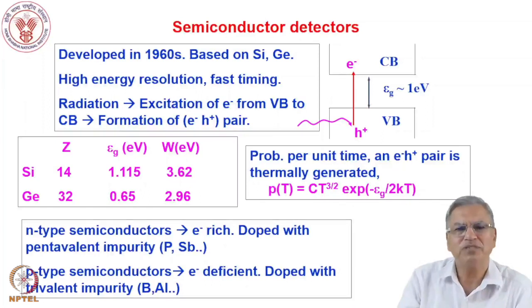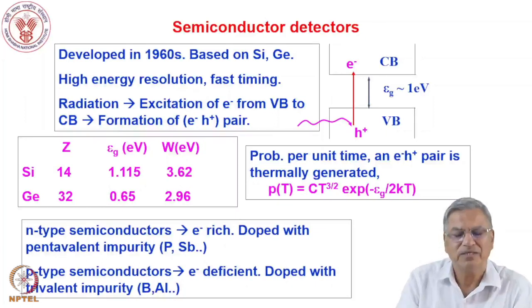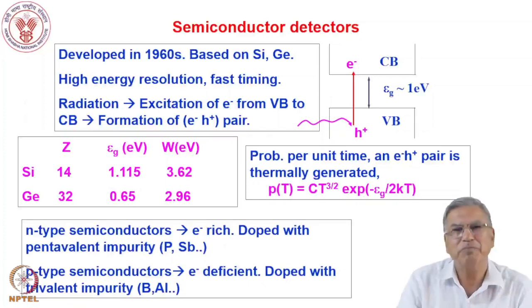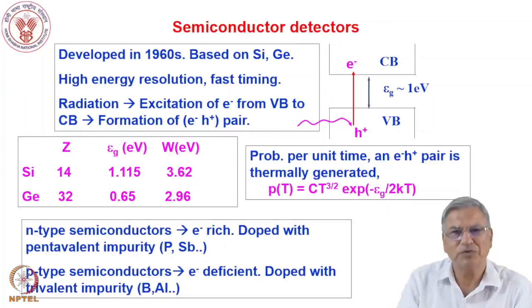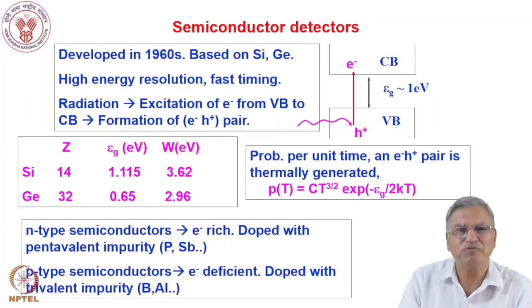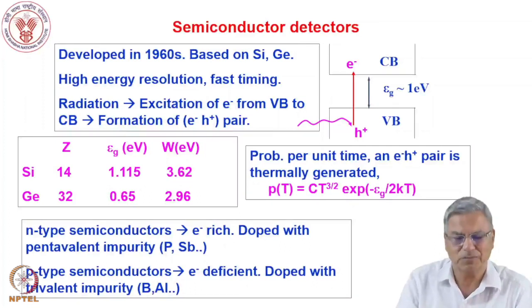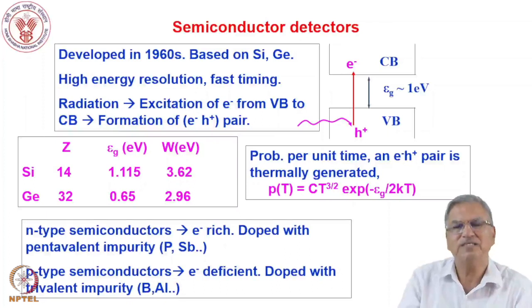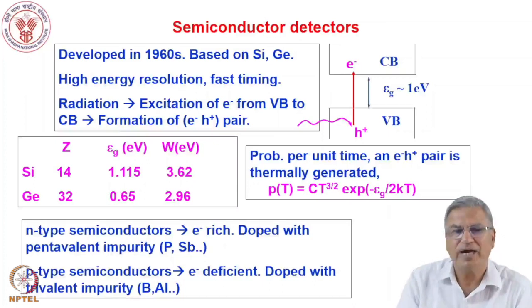The basic principle of semiconductor detectors is similar to gas-filled counters like ionization chambers. In ionization chambers, incoming radiation ionizes the gas medium, creating positive ions and electrons. In semiconductors, radiation falling on the detector material generates electron-hole pairs. Electron-hole pairs are analogous to the positive ion and electron pair in a gas detector. The semiconductor detector functions by collecting electrons and holes at their respective electrodes.